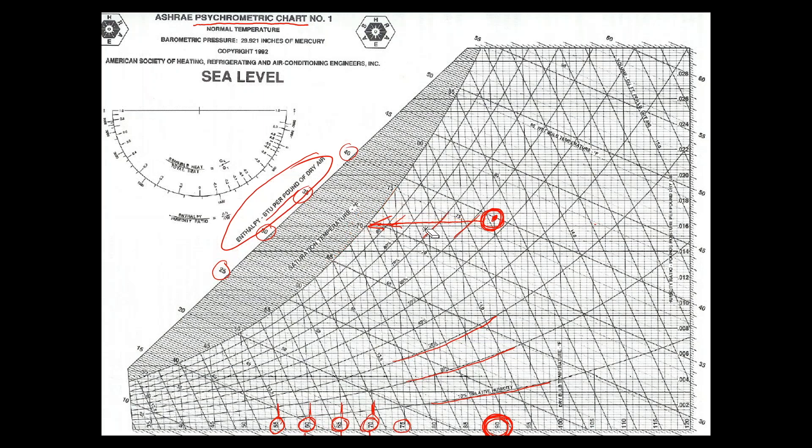Now, another interesting thing, I mentioned that we would focus on the enthalpy. Okay? So, let's take a look at what the enthalpy of this original air was. The enthalpy, you go this direction. Okay? And this is going to tell you the total energy content of that air. In this case, it's about 40 BTUs per pound of dry air.